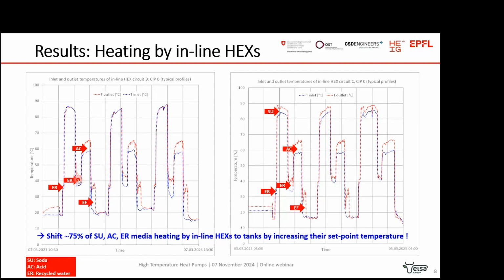So it seems that if we look at this graph, the temperature set point of the acid tank is too low, and it is systematically heated by the inline heat exchanger. We also see that the recycled water tank, which is not heated, is on average too low, so it is also heated by the heat exchanger.